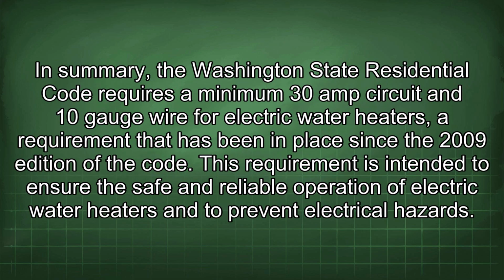In summary, the Washington State Residential Code requires a minimum 30-amp circuit and 10-gauge wire for electric water heaters, a requirement that has been in place since the 2009 edition of the code. This requirement is intended to ensure the safe and reliable operation of electric water heaters and to prevent electrical hazards.